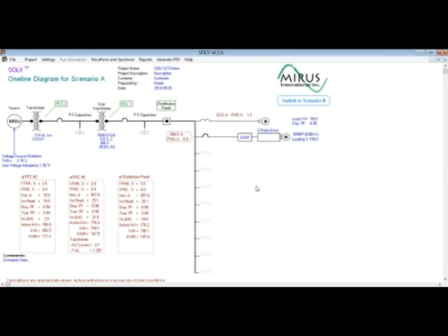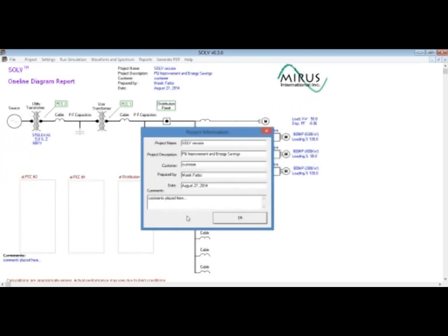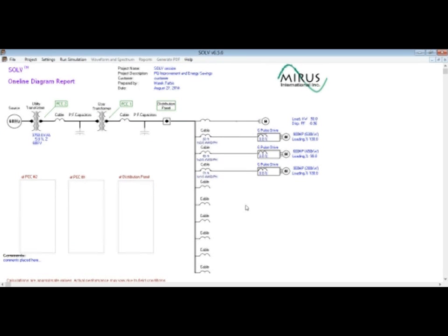And now that you are familiar with the scenarios and how to do energy analysis, I will demonstrate what effect a power system source impedance will have on the current and voltage harmonic distortion. So in this case, I load another example file I have prepared before, and we have 3 variable frequency drives and some linear loads, 1800 horsepower total power of the nonlinear loads, and they are supplied from a 3750 kVA transformer with 5% impedance, which is considered a rather stiff source.